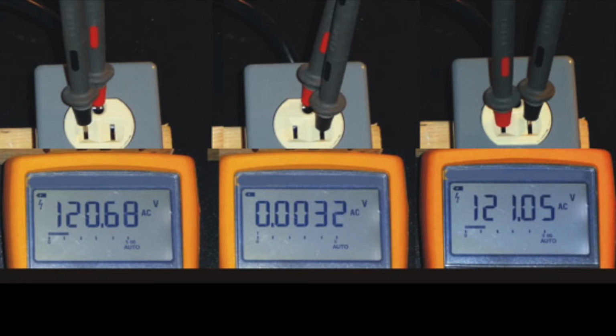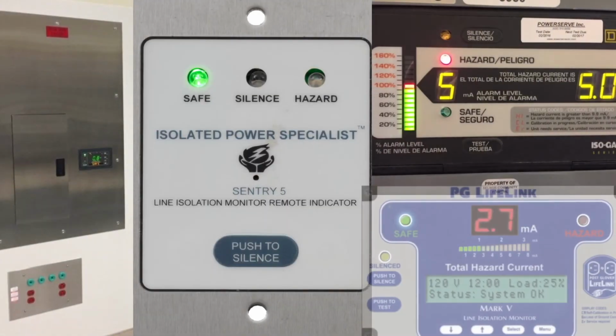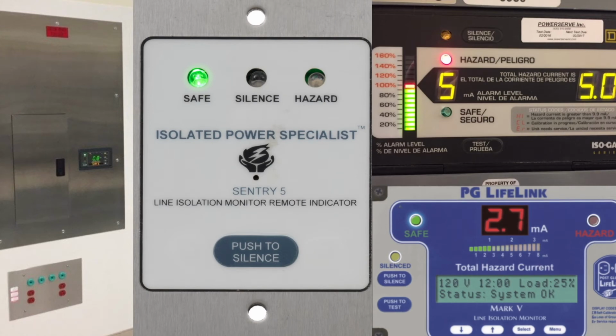Now let's talk about what makes an isolated electrical system different than a traditional system. An isolated electrical system has a steel enclosure, and inside that steel enclosure, you'll find something that looks very similar to the circuit breaker at your house. In addition, there is a line isolation monitor. The monitor detects what the potential leakage current can be. Anything above 5 milliamps is considered potentially hazardous. Now, just because a line isolation monitor alarms doesn't mean danger is present. It just means there's a potential hazard, but no one has necessarily been shocked yet. However, the chances have increased.